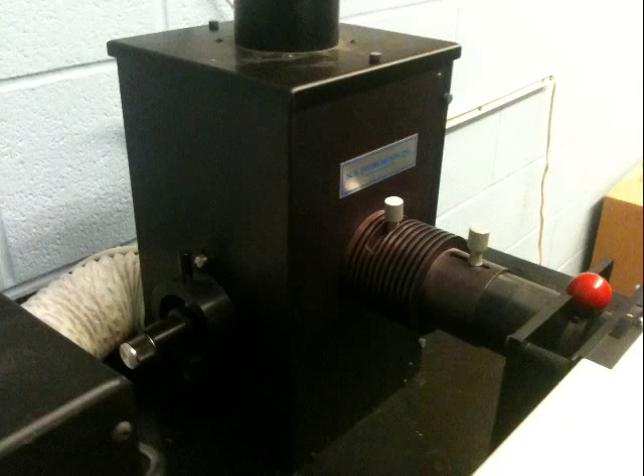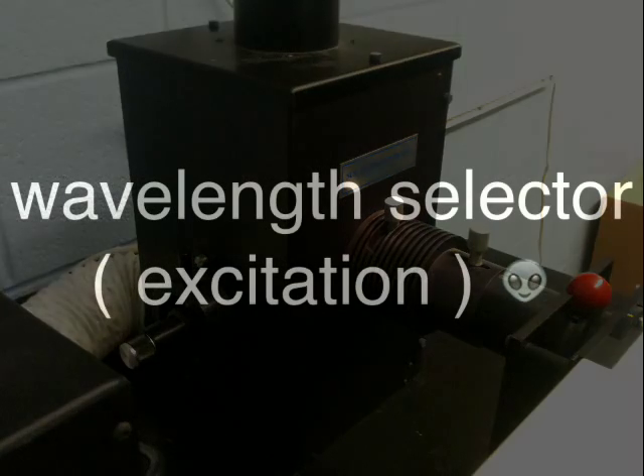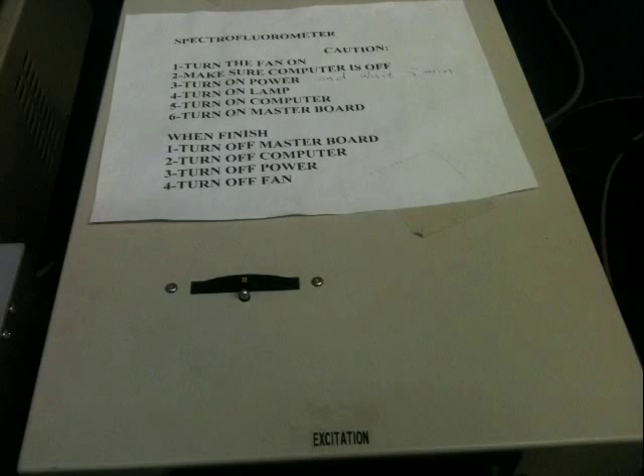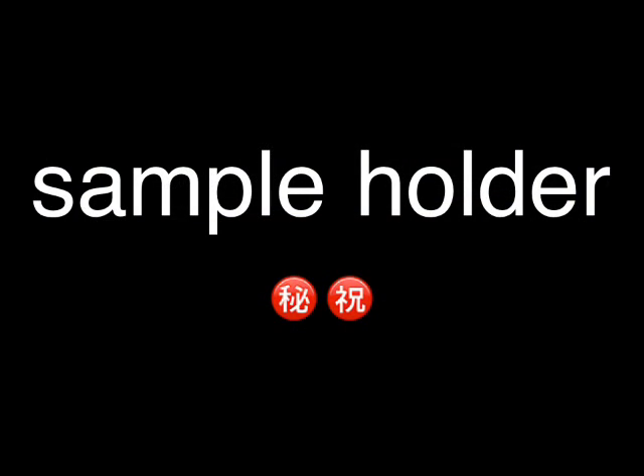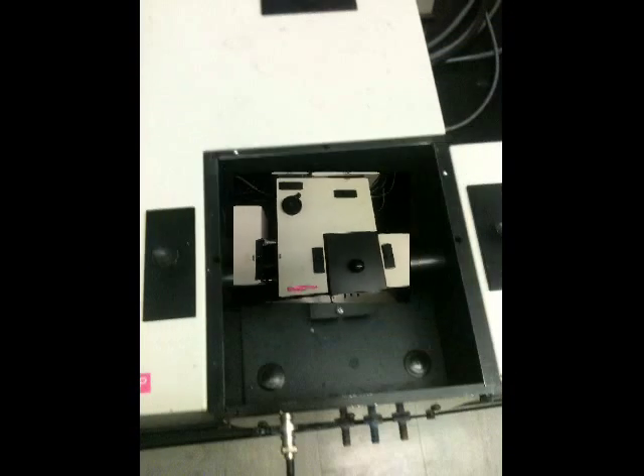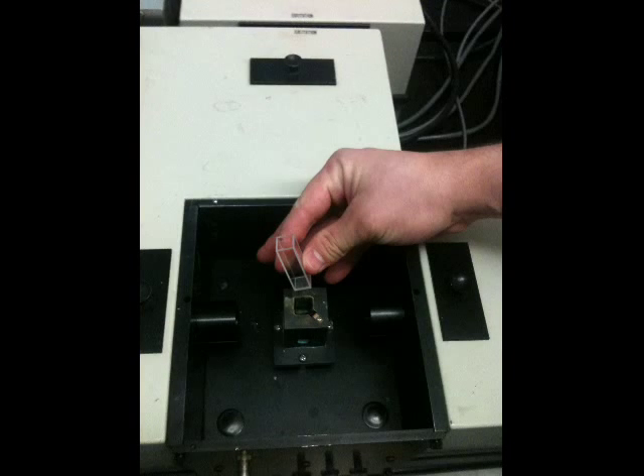This source fires radiation through that tube into a wavelength selector. The wavelength selector shown here will take that radiation source and select one wavelength set for excitation of the sample. The sample holder shown here is what holds the cuvette which the sample is in. As you can see from that open port in the back, that is where the wavelength will come through and excite the sample.